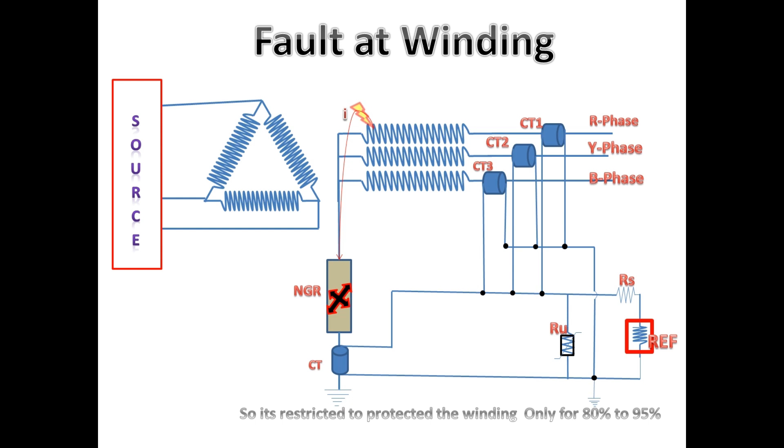This REF will not be able to activate for this lesser value. Due to this, the REF is not able to protect 5 to 20% of the neutral side of the winding, and it can only protect 80 to 95%.